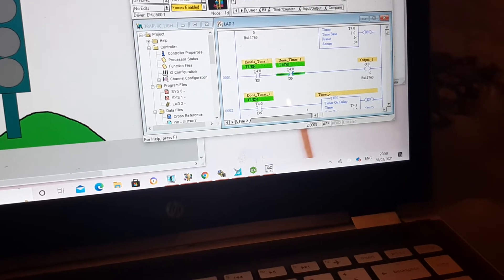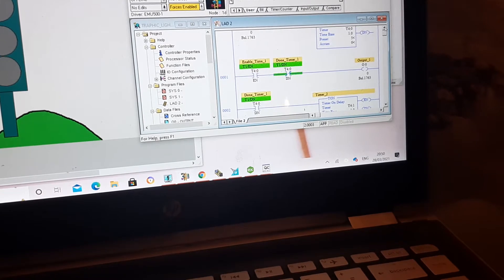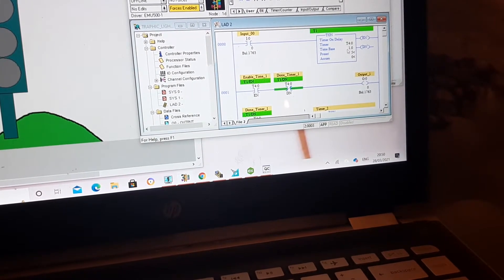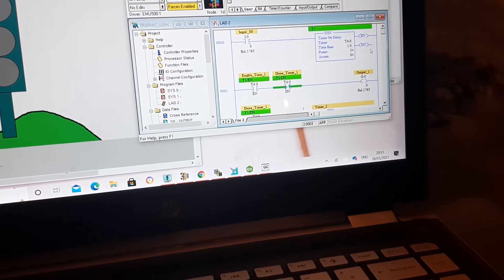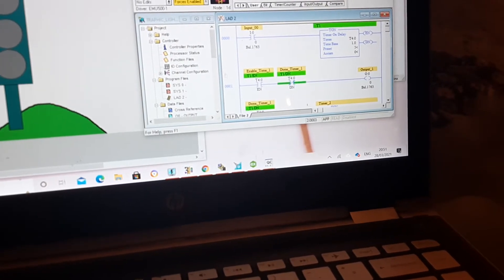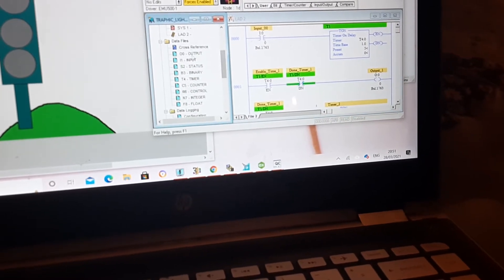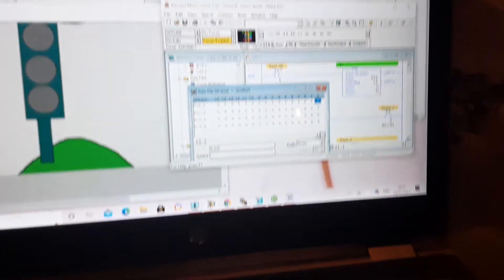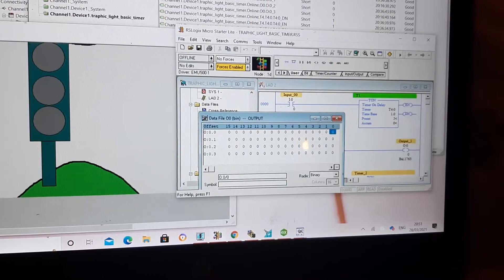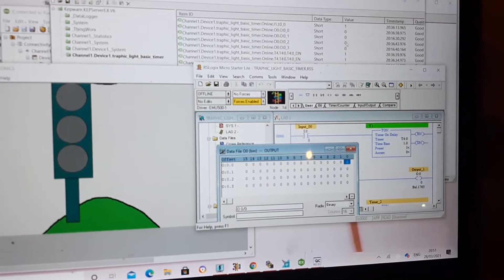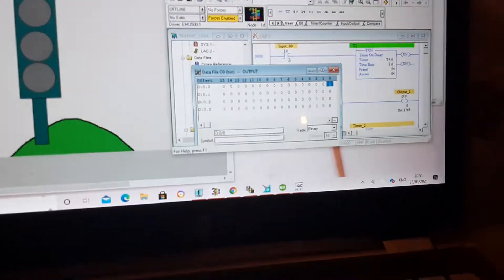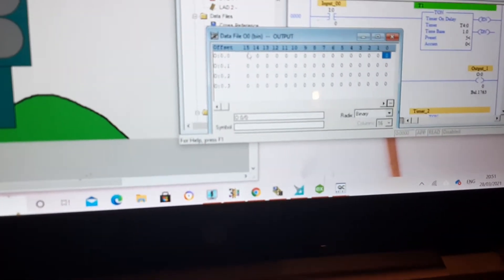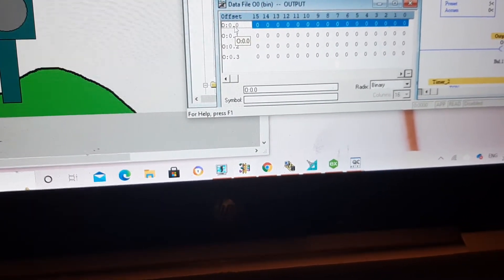If you are using the output, if you have different type of program and if you use the done pin or enable pin of the timer directly, you won't see the issue that I'm going to describe. But if you are using the O bits from the output here, what you would see on Quick Client is that it is very important how you use the address. Otherwise, instead of one and zero, you will see bytes. So you are not going to have bit here, you are going to have bytes. And the reason is because when you look at the category of O, you would see that we have four categories.